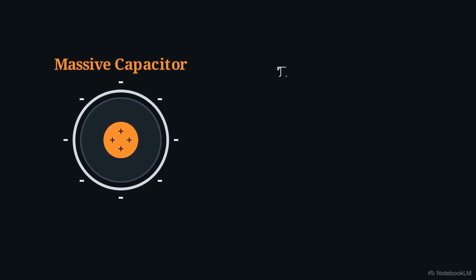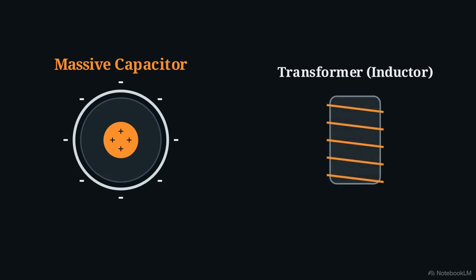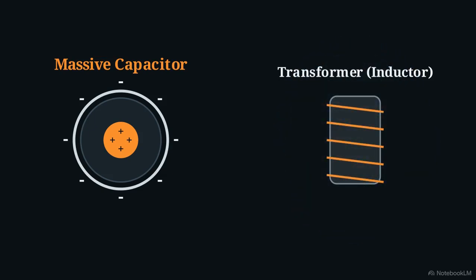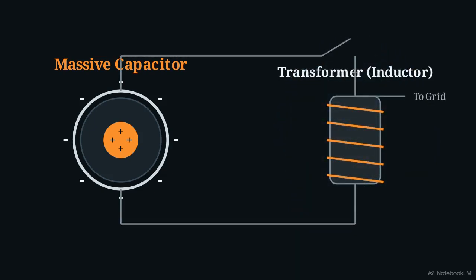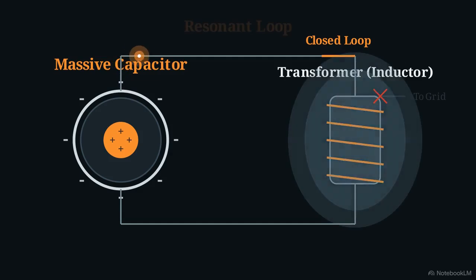Because of how they are constructed, these long cables inadvertently act as a massive capacitor, meaning they excel at storing a vast amount of electrical charge along their length. Wired directly to that cable is the wind turbine's transformer, an inductor with a nonlinear magnetic core. Instead of holding raw electrical charge, it stores energy in a fluctuating magnetic field. When that circuit breaker jams, it forces this capacitor and inductor into a closed circuit.